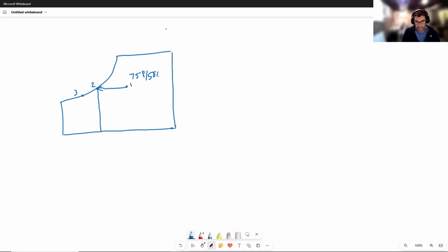The dry bulb temperature at state 3 is going to be lower than the dry bulb temperature at state 2. But now we also strip moisture out of the air, because if we continue horizontally, we'd go off the chart. That's not possible. So we have no choice but to slide down the curve in order to stay on the chart. So this is 100% saturated air at T2 dry bulb, but as we slide down, we end up with 100% saturated air at T3.